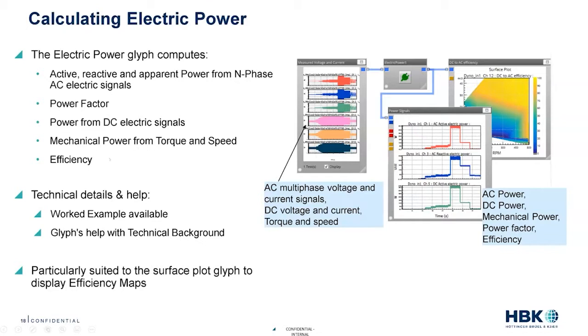So if it's got all this data, the active AC power and the DC power, it can calculate the efficiency between DC and AC, in other words, the efficiency of the inverter. If it's also got the mechanical power, it can calculate the efficiency of the motor by dividing the mechanical power by the AC power. So based on what it's getting as input, it'll calculate all it can.